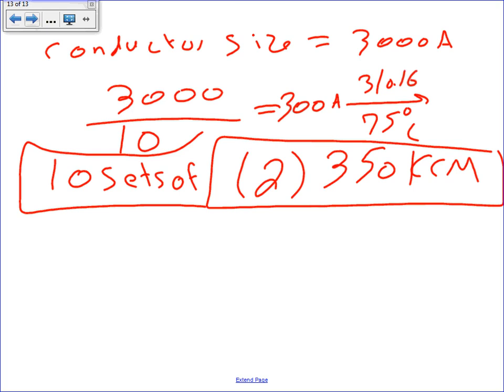Or you can, most likely at this size, guys, you need to derate. Why derate? It saves you money. So we're going to go back and size our conductor right on the steps, guys. You're going to see it's going to be very easy now because we have everything calculated. I'll show you how easy that would be.